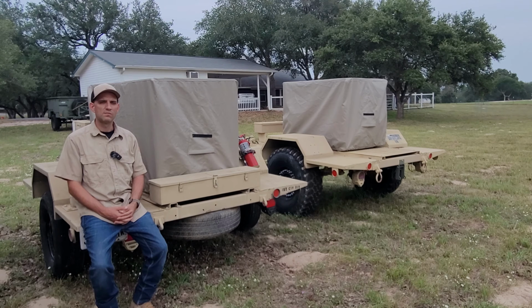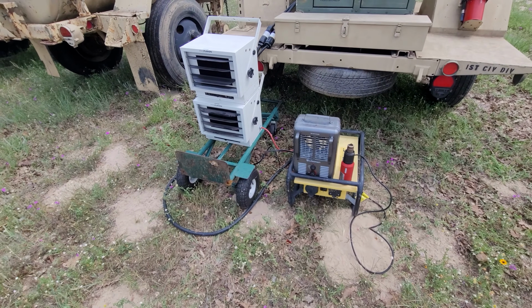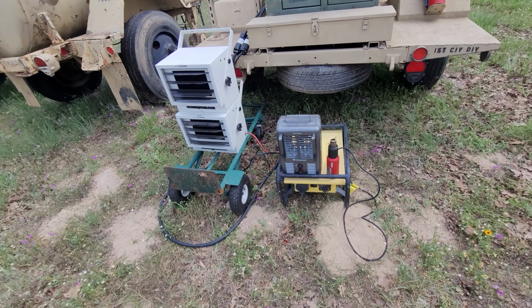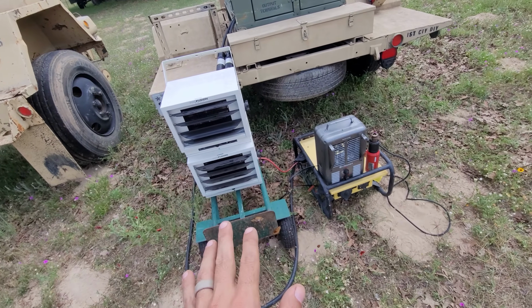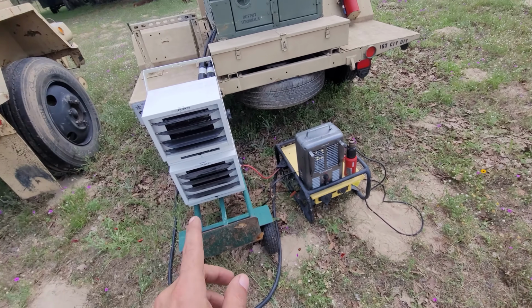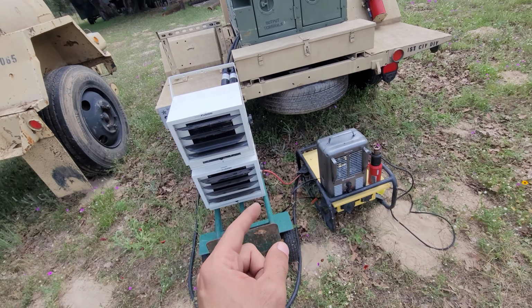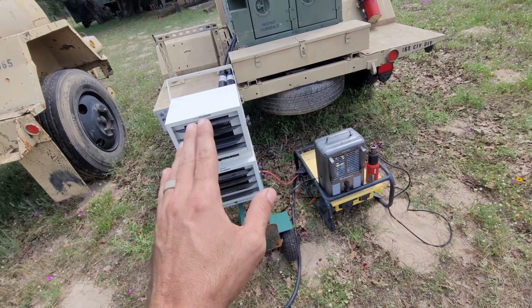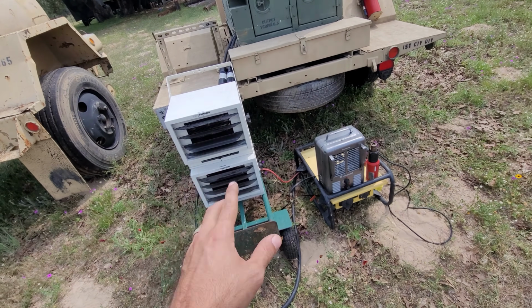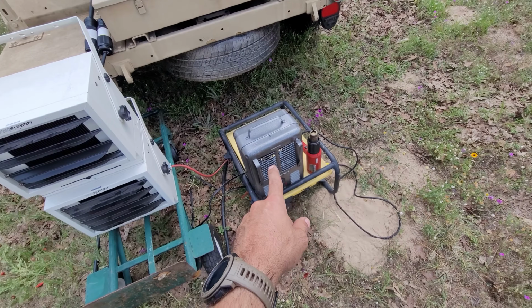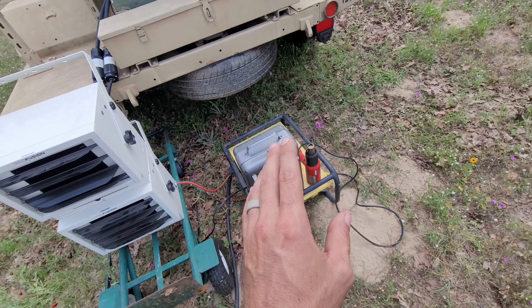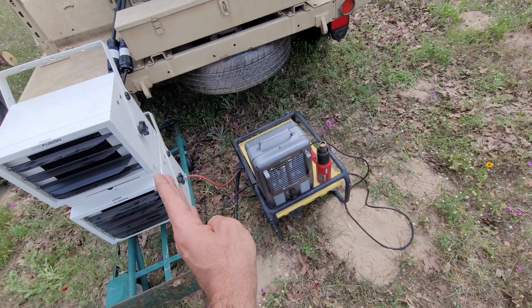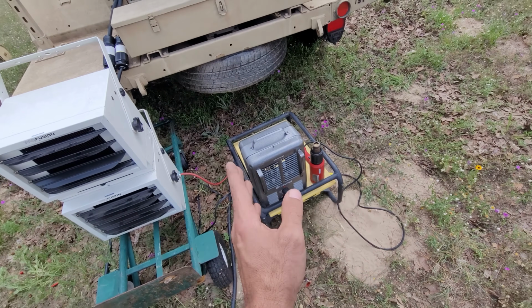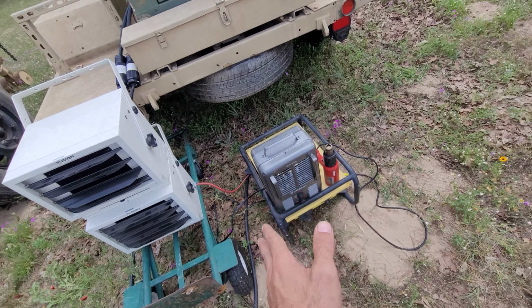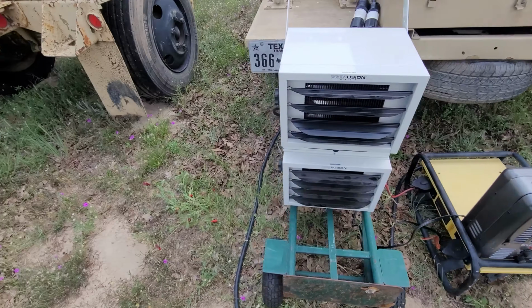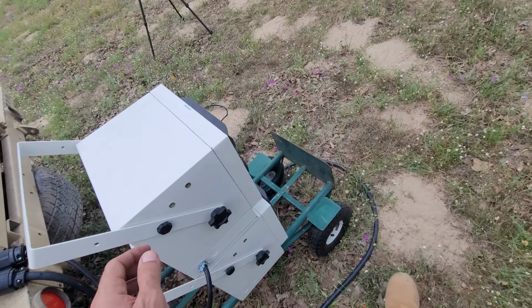Eventually, I'm going to get an actual good load bank, but quickly I'm gonna talk about this. In my opinion, I think using electric heaters is the best way to do this, because you know exactly how much power it's gonna put out. It is a 1 power factor, and if it's a 5,000 watt heater, for example, at 240 volts, it's gonna pull 5,000 watts. If it's a 110 volt heater at 1,500 watts, it's gonna pull 1,500 watts. You don't need to worry about it when it starts surging really high or it being some weird anything. It is what it is. And then you can look on the panel if you're unsure, say like you bought it used or something like that.